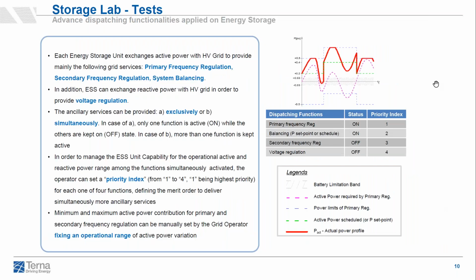Indeed, the ESS installed in the storage lab are capable of providing, as we said, different grid services. And Terna can control and also configure the features of these services remotely. So the ancillary services can be provided one by one or simultaneously, always respecting the limits of the ESS in terms, for example, of available capacity. So in order to properly control the ESS, Terna can activate or deactivate functions according to the grid status, and also Terna can assign a priority index from 1 to 4 to each function in order to manage the ESS, for example, for active or reactive power priority.